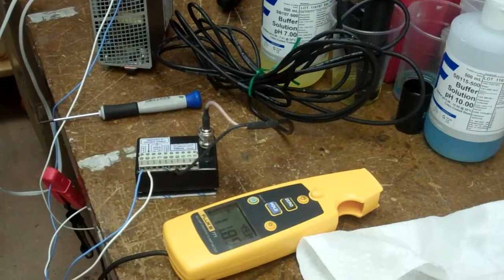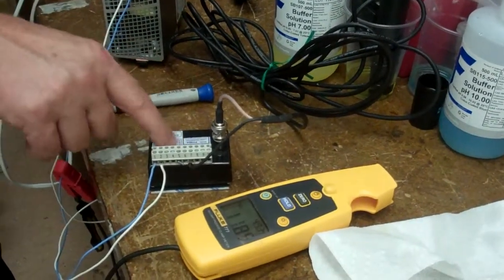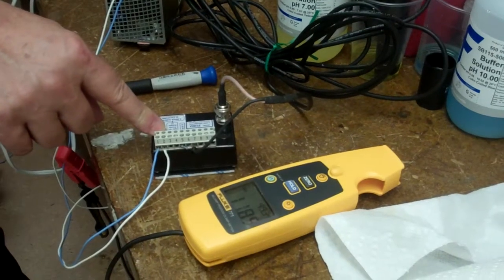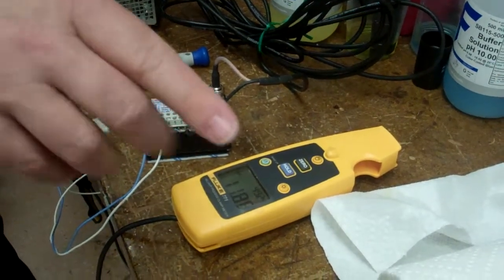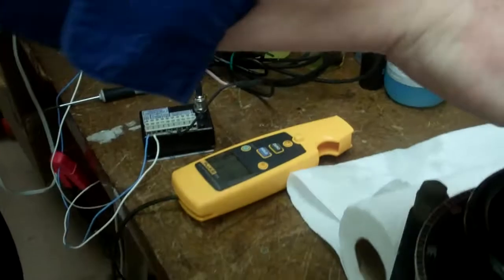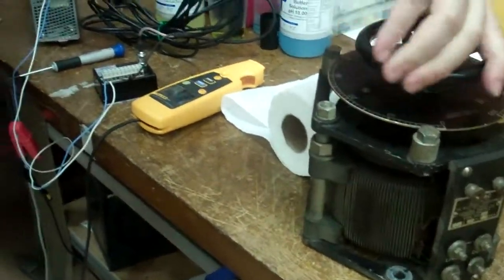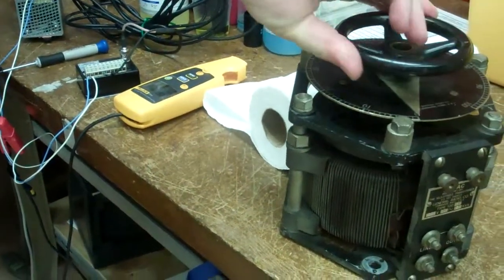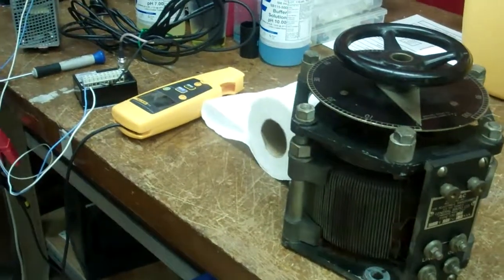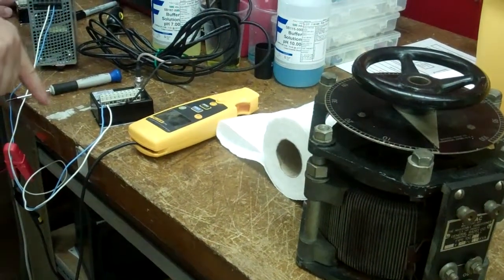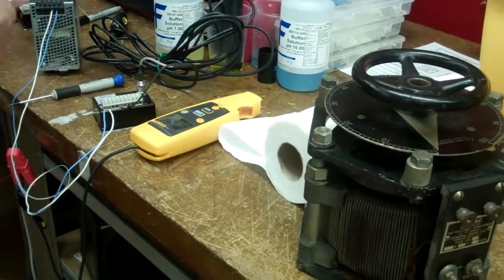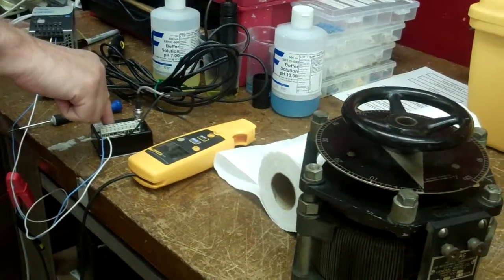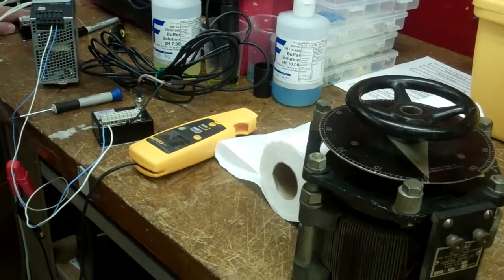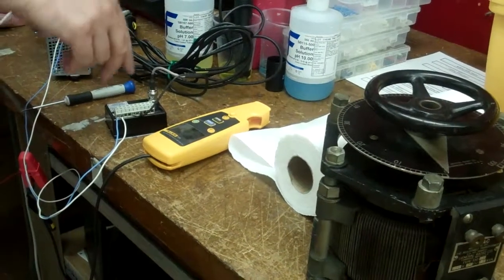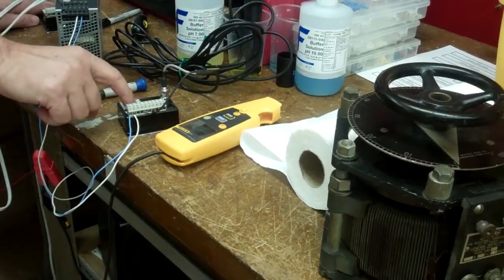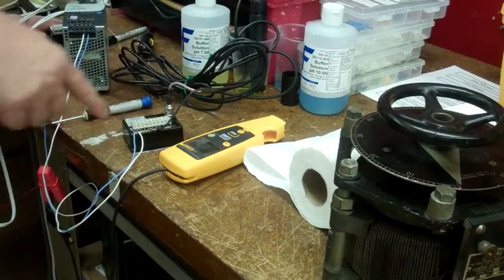So that's the end of how to bring these back in. Turn these counterclockwise 25 times. It turns the rheostat from wherever it is all the way to one end. So counterclockwise 25 times. You turn the span clockwise 4 times. Turn the 0 clockwise 5 times. It puts you in the approximate range as you now see is starting to calibrate.